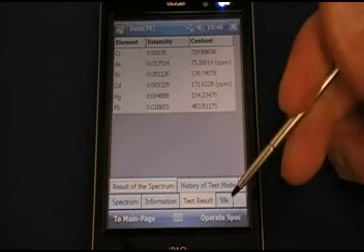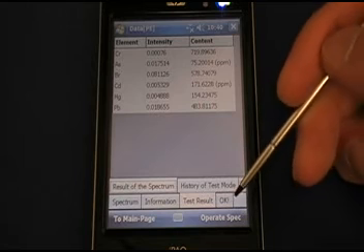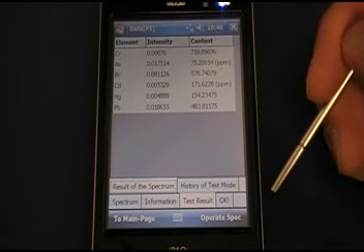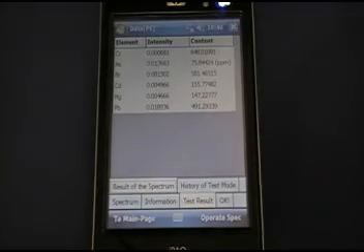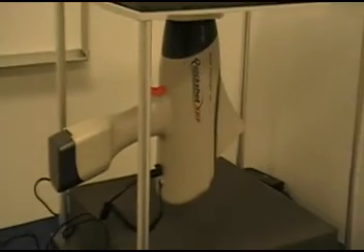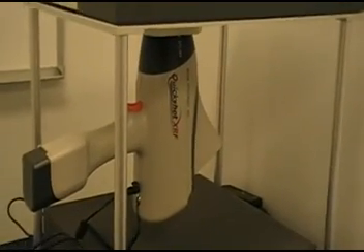Good accurate results, nice and fast, and that can be changed from 30 to 300 seconds, even shorter for certain applications. And that's a brief overview of the QuickShot XRF handheld analyzer calibration procedure.